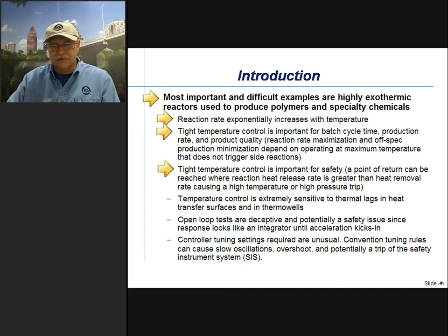Reaction rate maximization and off-spec production minimization depends on operating at the maximum temperature that does not trigger side reactions of off-grade or undesirable products. Tight temperature control is important for safety — a point of no return can be reached where reaction heat release is greater than heat removal, causing a high temperature or high pressure trip. Temperature control is extremely sensitive to thermal lags in heat transfer surfaces and in thermal wells. You have to be awfully careful; the process may in fact run away from you if there are seemingly insignificant thermal lags due to fouling of heat transfer surfaces or improper design of thermal wells.